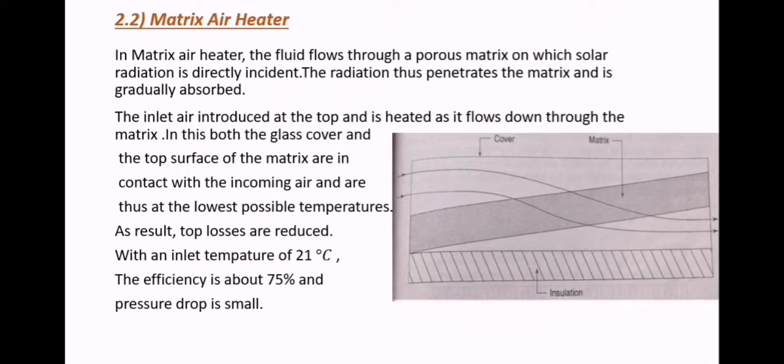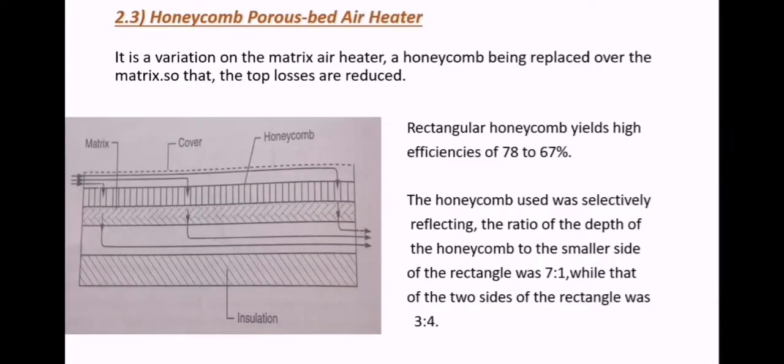The pressure drop in the matrix is also very small. It is estimated to be only 1/200 times that in the passage of a conventional heater. However, it is to be noted that the above estimates require a uniform flow through the matrix. This is rather difficult to achieve.